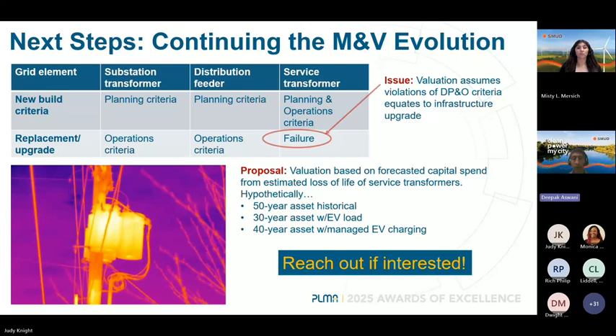Service transformers serve fewer customers than substations and feeders. A typical residential service transformer might serve 5 to 20 customers, probably closer to 10 on average. With that small number of customers, you don't see as much load diversification, so they see quite a bit of variability in overall load, and they're designed to handle that. So when you see an overload or violation of operational criteria, that transformer may still operate just fine for another 10 or 15 years.